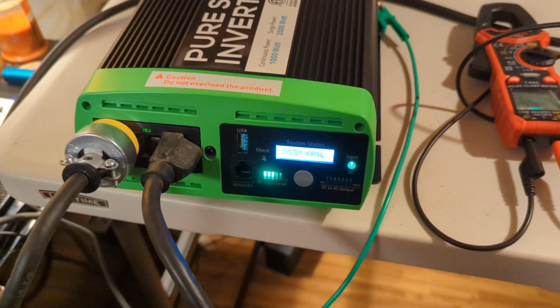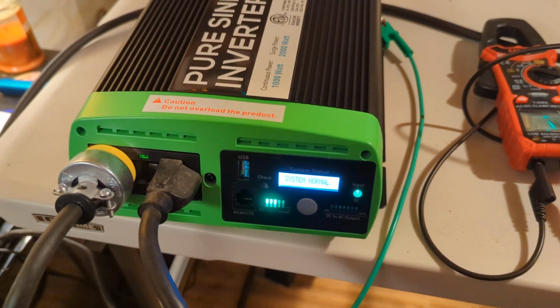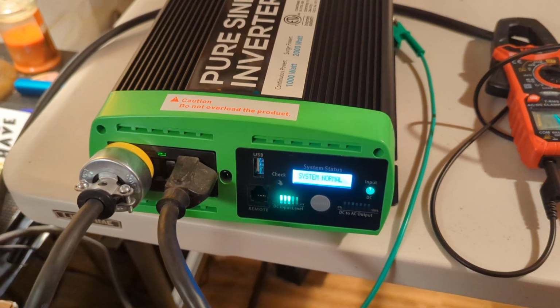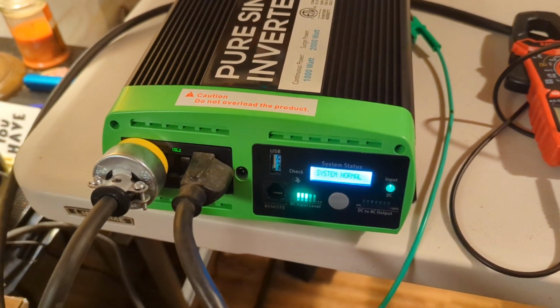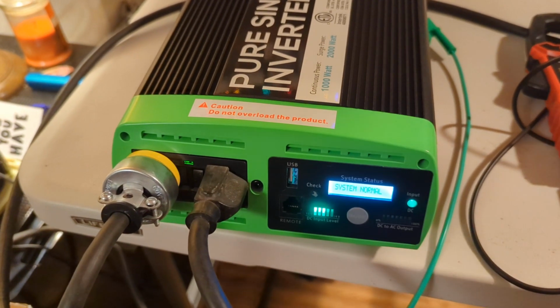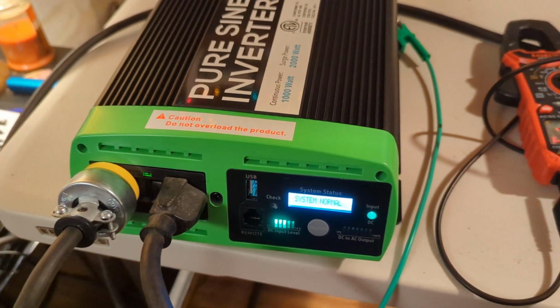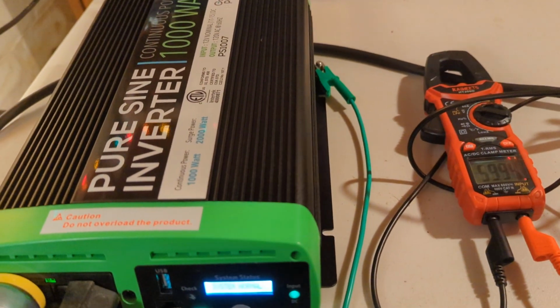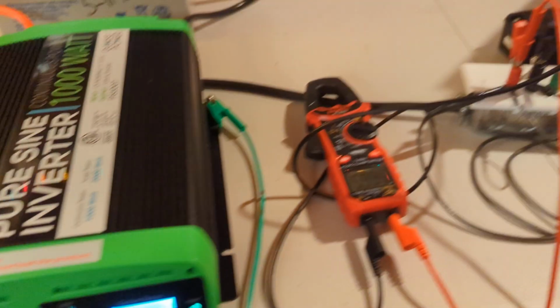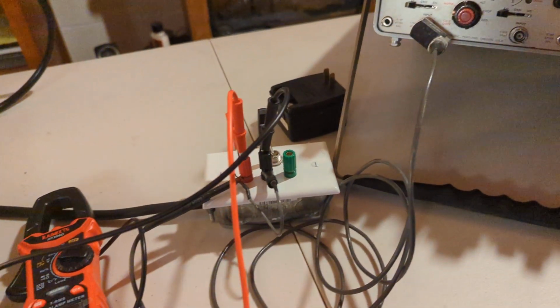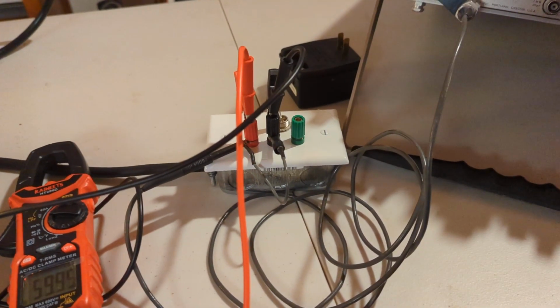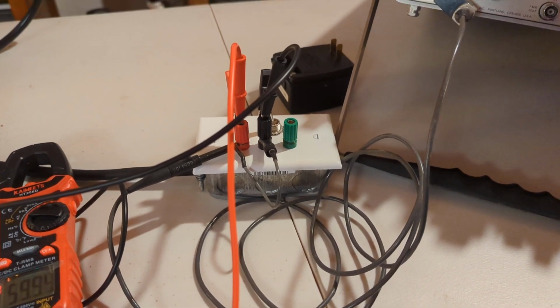Again, no floating neutral, which is in my book much safer for anything AC that's plugged in, because there's no voltage being carried on the neutral side. So when you flip off the light switch, there really is no voltage present at the light socket, or at least there shouldn't be. I have a much higher level of confidence with that.